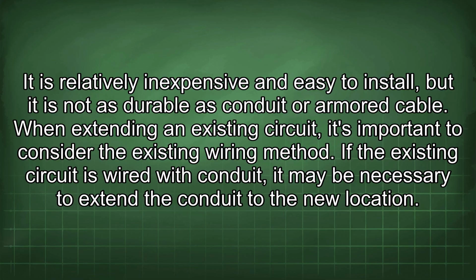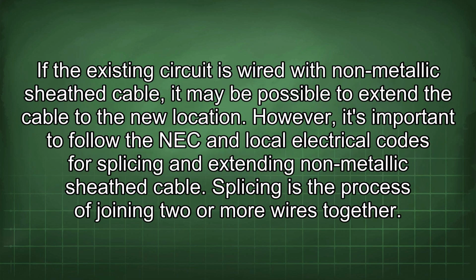When extending an existing circuit, it's important to consider the existing wiring method. If the existing circuit is wired with conduit, it may be necessary to extend the conduit to the new location. If the existing circuit is wired with non-metallic sheath cable, it may be possible to extend the cable to the new location. However, it's important to follow the NEC and local electrical codes for splicing and extending non-metallic sheath cable.